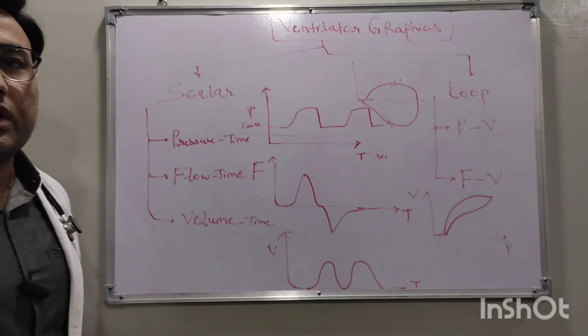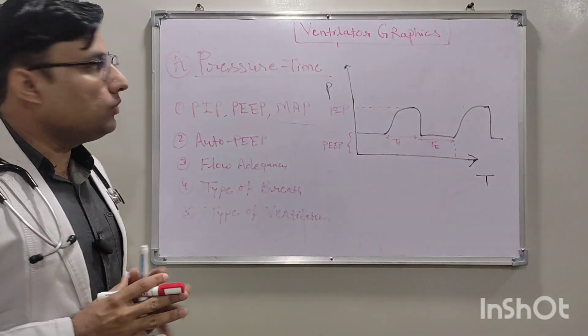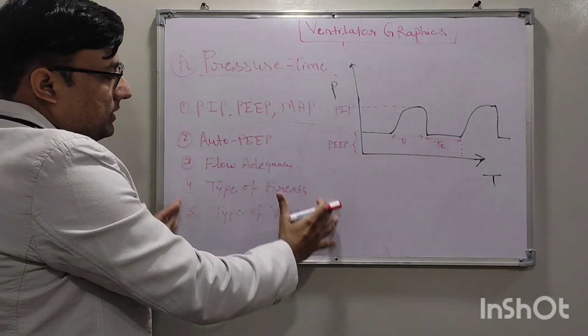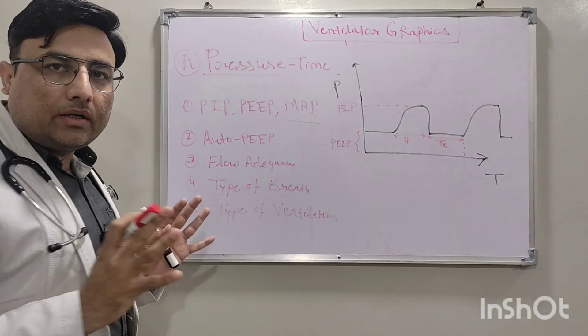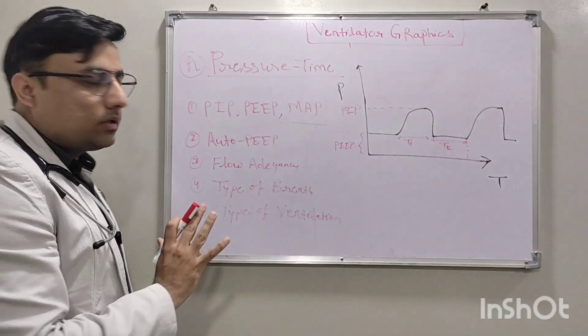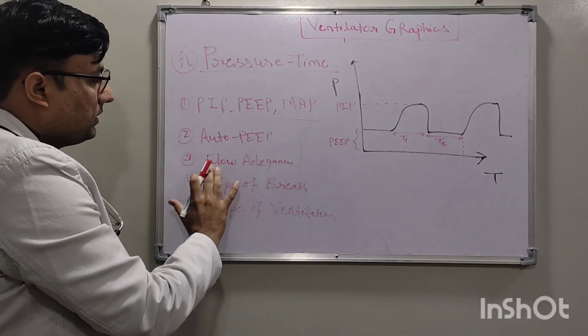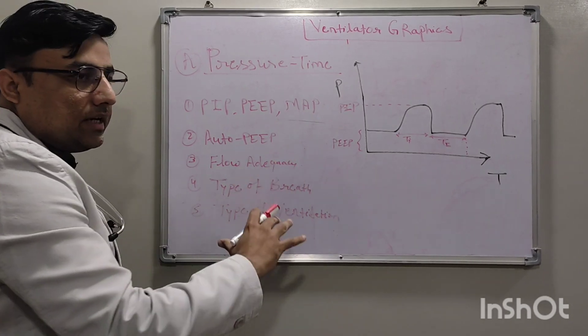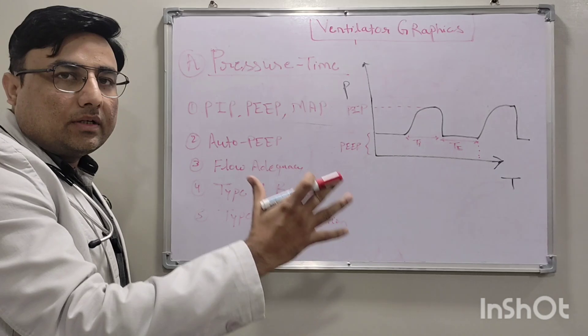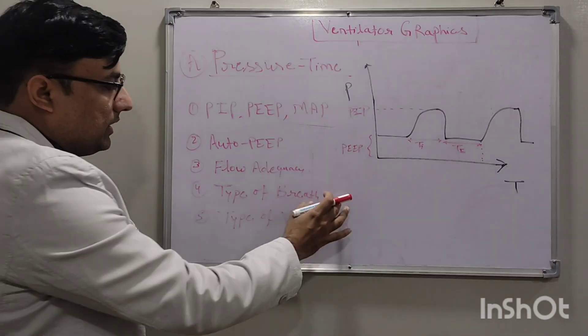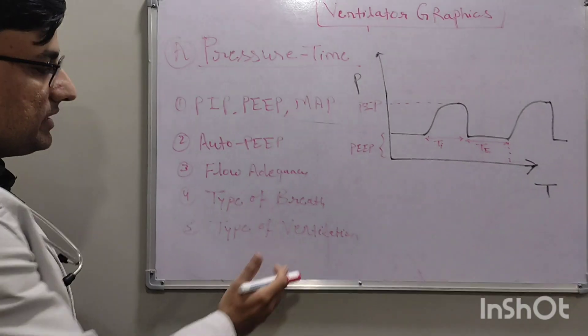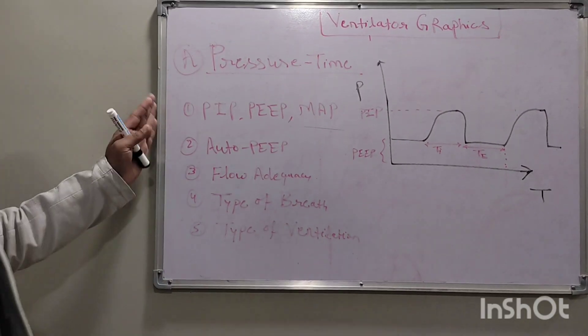Today we will discuss about the pressure-time curve. In the pressure-time scalar graphic, the things we can interpret are: PIP, PEEP, and mean airway pressure. We can also detect auto-PEEP, assess flow adequacy — whether flow is less or excessive — identify the type of breath, whether it is mandatory or triggered, and determine the type of ventilation, whether it is pressure control or volume control.